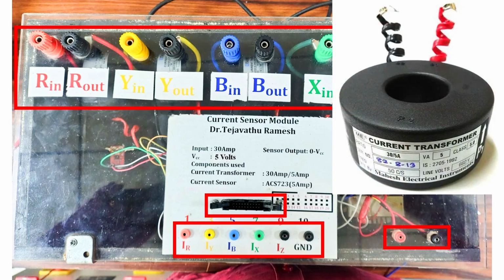I used a 30 ampere by 5 ampere current transformer along with a 5 ampere bidirectional ACS723 current sensor. The current transformer first steps down the motor current. So when 30 amperes flows on the primary side, we get 5 amperes on the secondary side. This 5 ampere current is then given to the ACS723 current sensor. In this way, by combining a 30 by 5 ampere current transformer with a 5 ampere ACS723 current sensor, we can design a low-cost 30 ampere current sensing module.